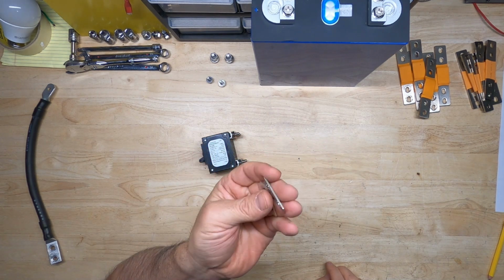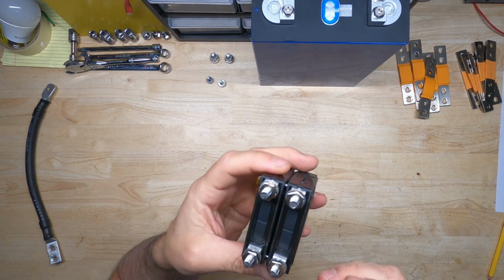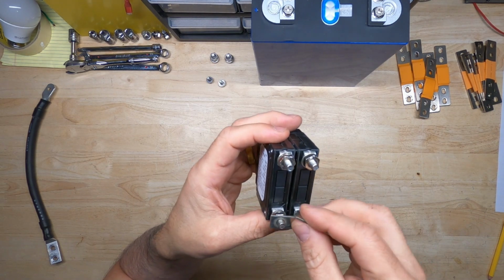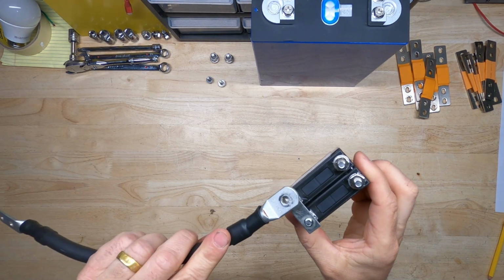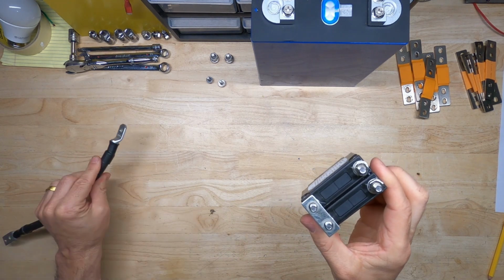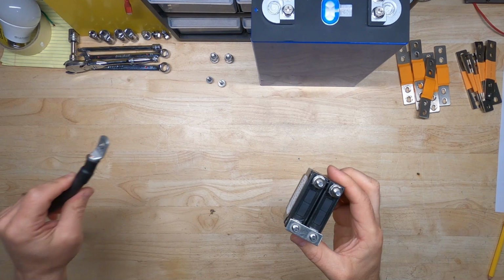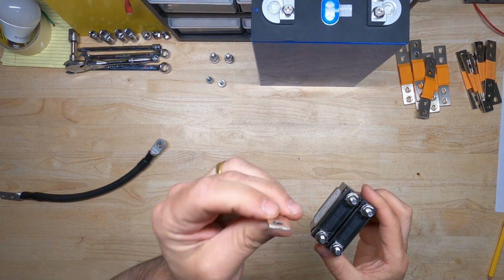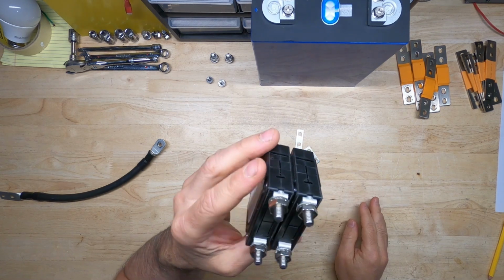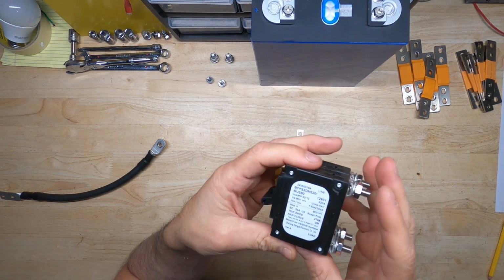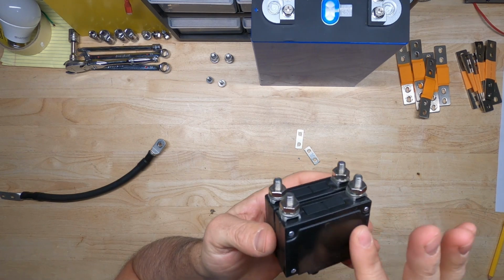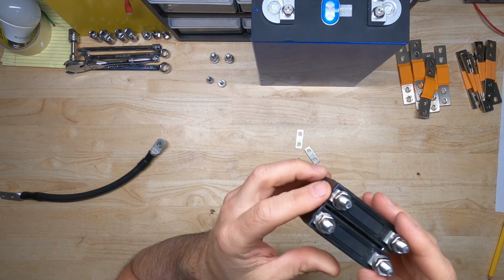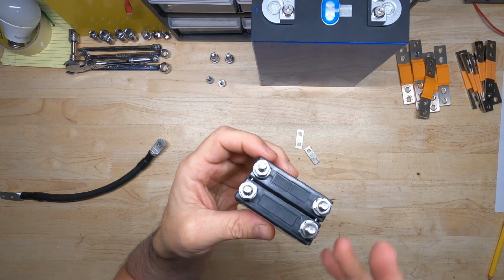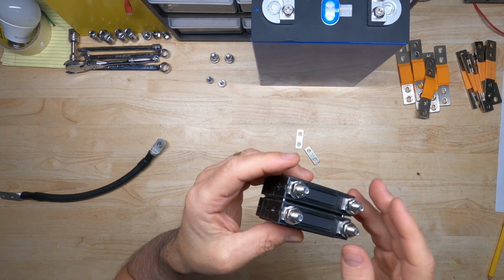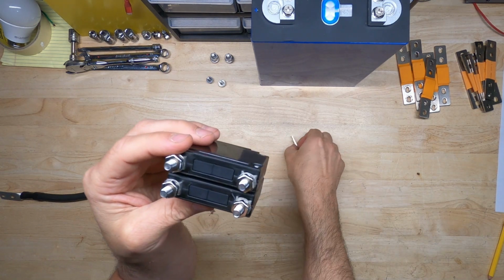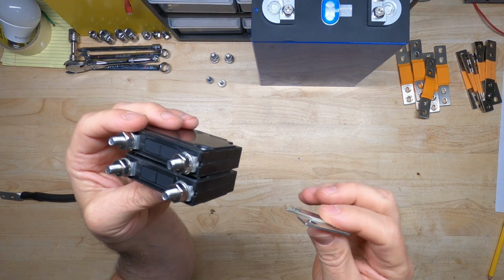As far as the shims are concerned, I don't see a reason for these. There's no good reason. Obviously in their design they have to have them in order to bridge the connection for the single lug cable. But if they use a double lug on both sides, this would not be a problem, and they can just get rid of these. There's no reason for these. It's just restricting the current. Although I didn't notice a huge difference in heat being generated. It's hard to tell because most of the heat is generated inside and just propagating through. But just looking at the video, I could see the heat profile slightly better without these. But yeah, so I give these, I don't know, we'll just say not needed.